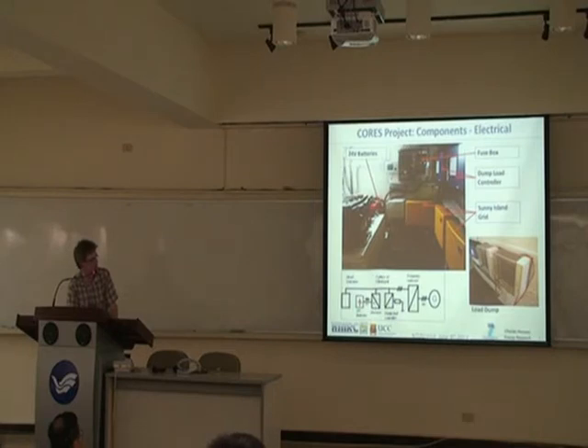So they create that grid, they create the synchronization for the grid, and they also control the charging of the batteries on board. There's also required to be a backup diesel generator, because there are many times when for several days there will be no waves and it will be very calm. In that situation, we need to maintain power to the onboard systems, the communication systems, the control systems, the DC, the bilge pumps. All of these systems need to be kept operational even when there are no waves. And so because we had no grid connection, we had to supply this backup diesel generator on board in order to keep the system operational.